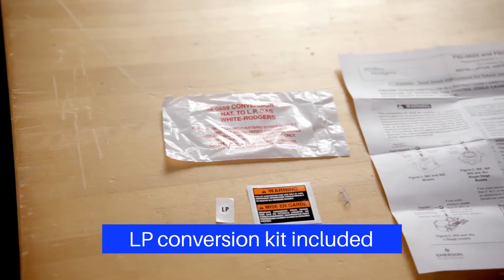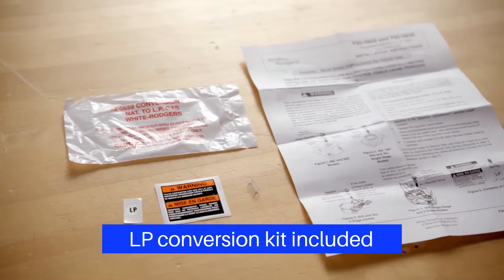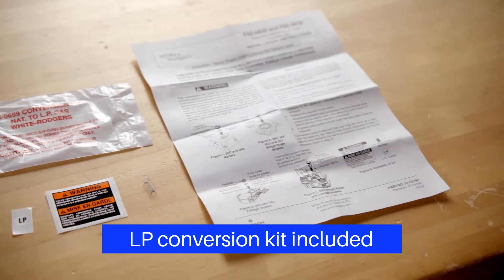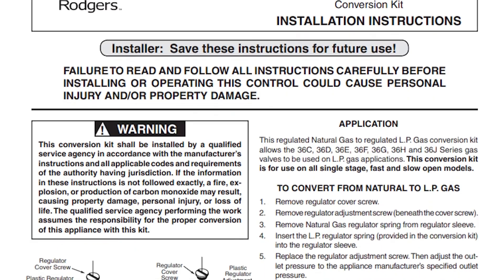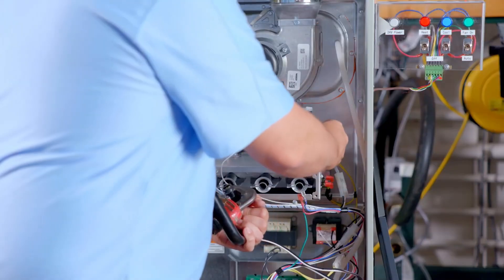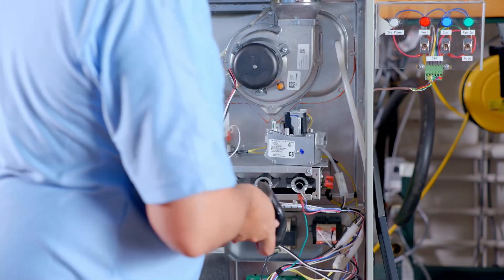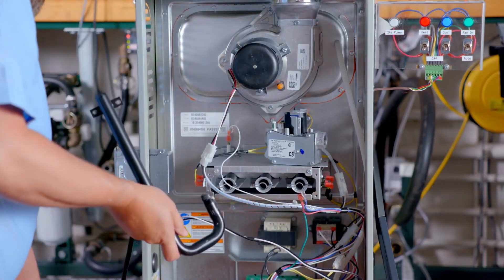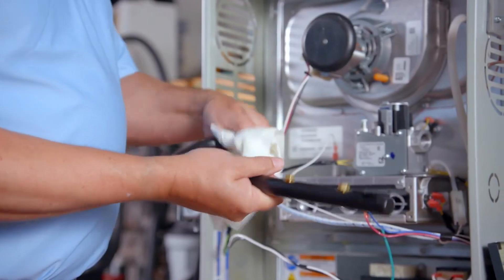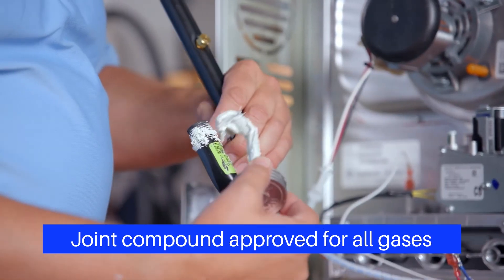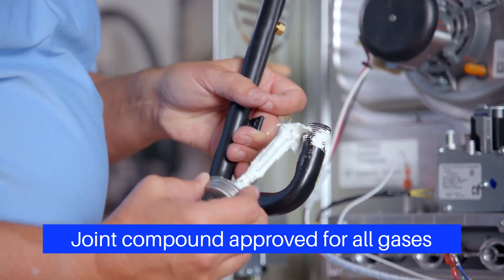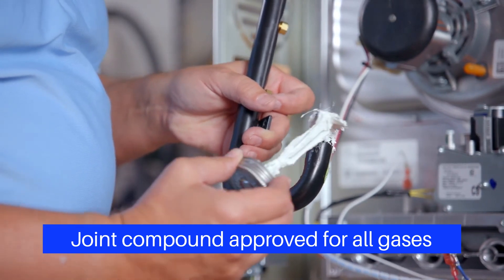The 36J22214 Regulator comes set up for natural gas. For liquid petroleum gas conversion, use the included White Rogers 920659 LP Gas Conversion Kit. Follow the conversion instructions included in the kit. For this application, natural gas is used so no conversion is needed. Clean the manifold threads and apply pipe joint compound that is approved for all gases only to the male threads of the manifold. Do not apply the compound to the first two threads.